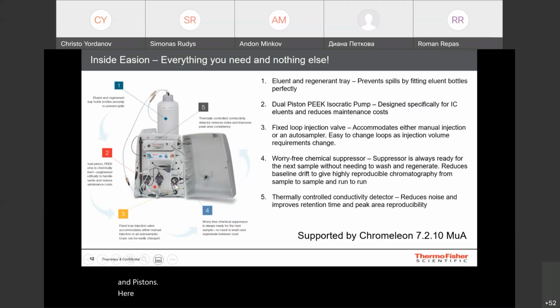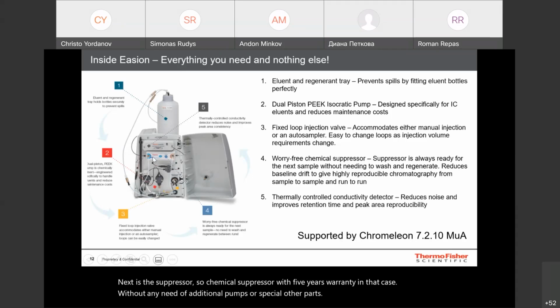Here you can see the injector. Only fixed loop injection is possible here, but you can easily change manually the volume of the injection loop. Next is the suppressor, so chemical suppressor with 5 years warranty in that case, without any need of additional pumps or special other parts. In series, there is our conductivity detector, which is thermally controlled. All the system is controlled by our Chromeleon 7.2 version of the software.